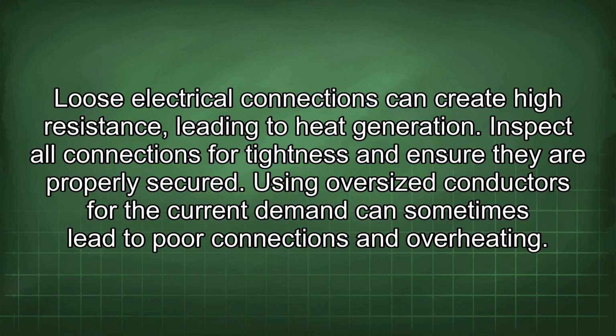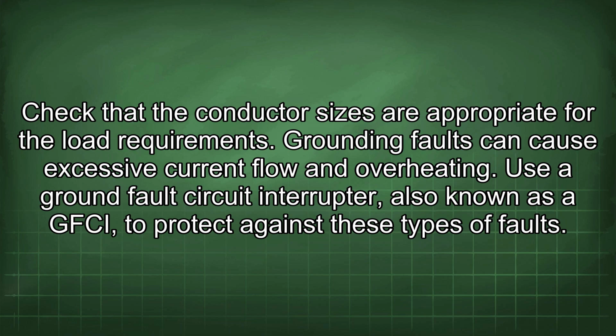Loose electrical connections can create high resistance, leading to heat generation. Inspect all connections for tightness and ensure they are properly secured. Using oversized conductors for the current demand can sometimes lead to poor connections and overheating. Check that the conductor sizes are appropriate for the load requirements. Grounding faults can cause excessive current flow and overheating. Use a ground fault circuit interrupter, also known as a GFCI, to protect against these types of faults.